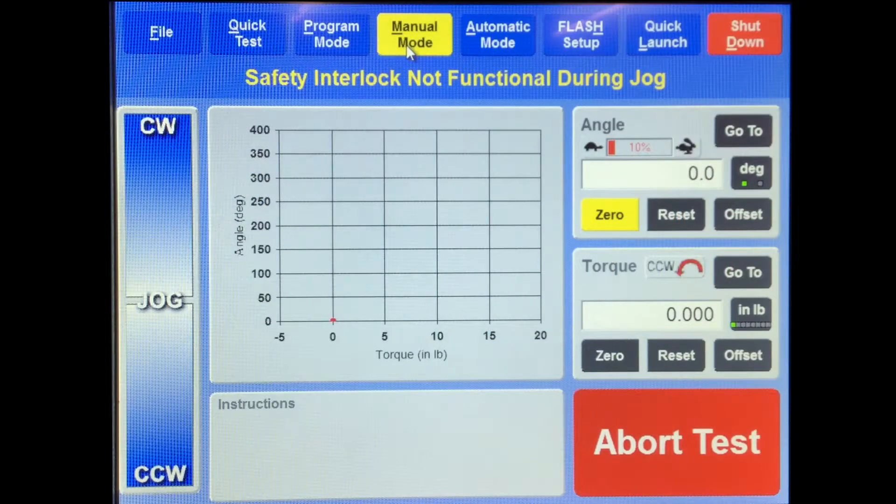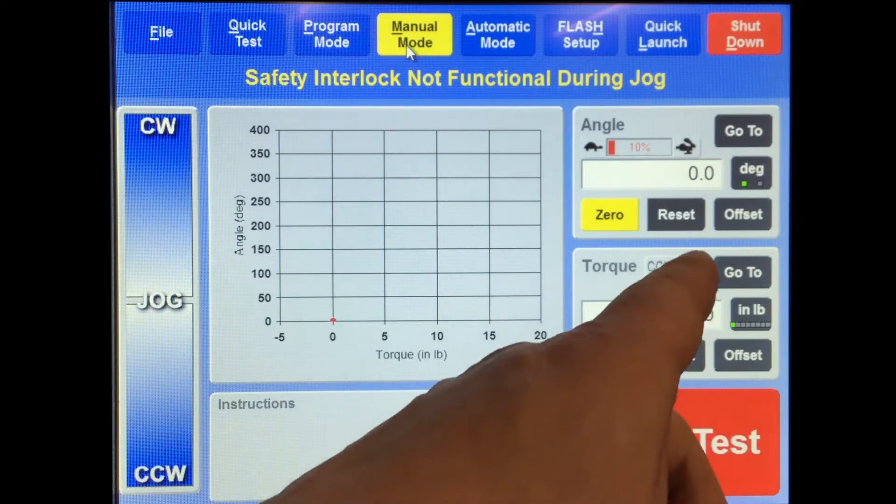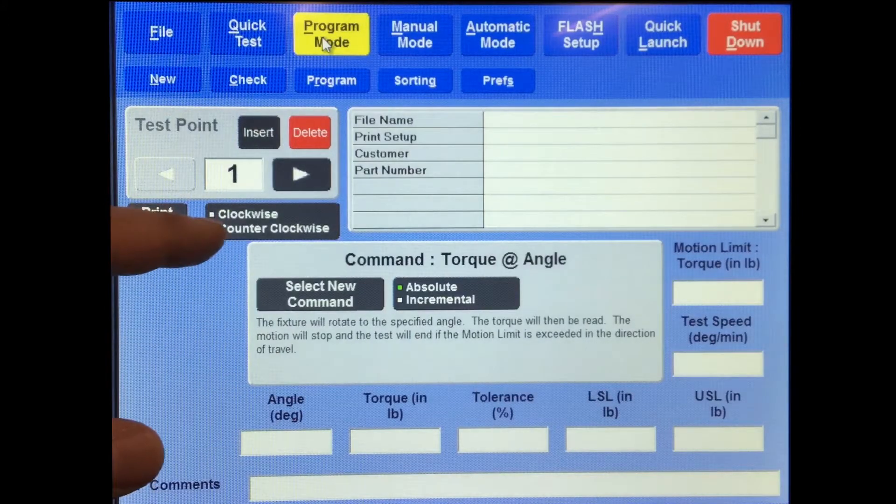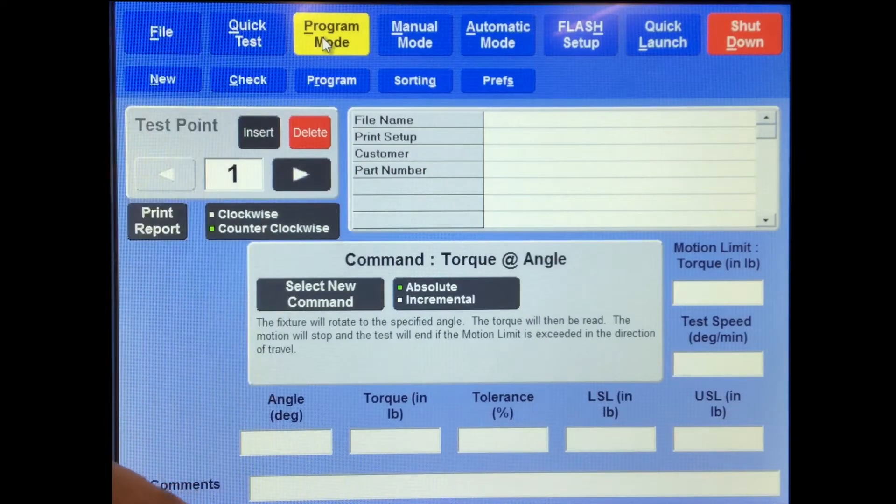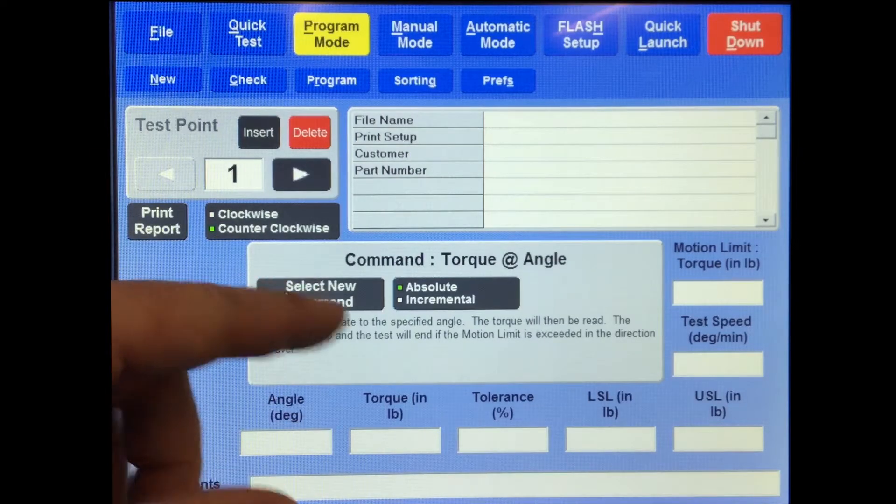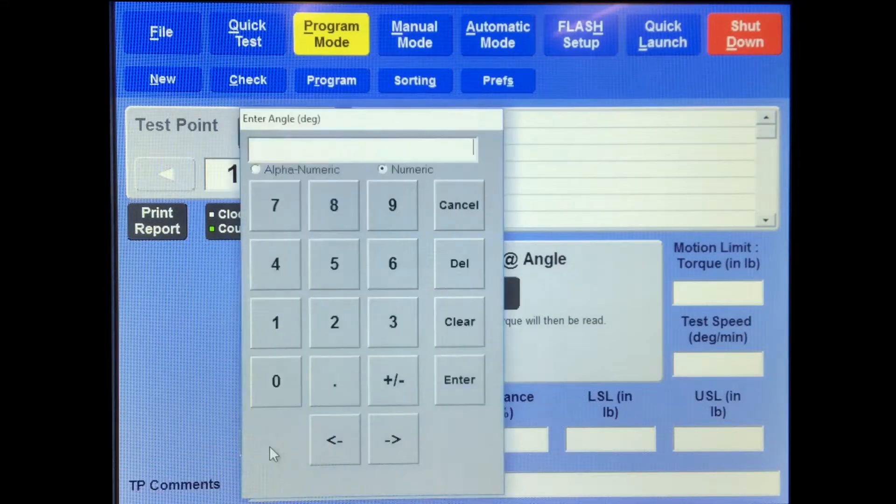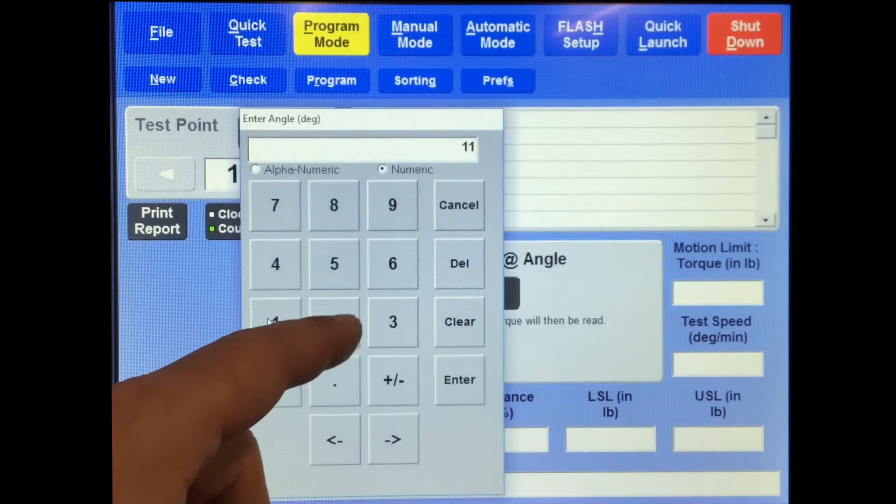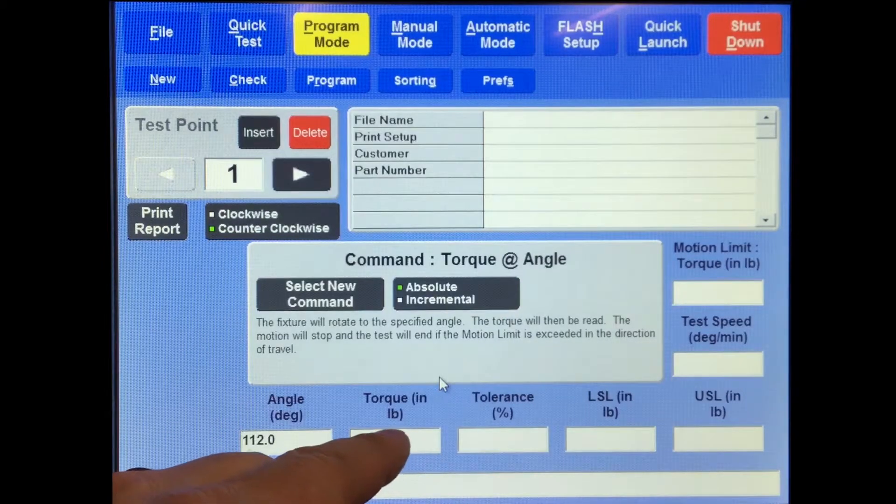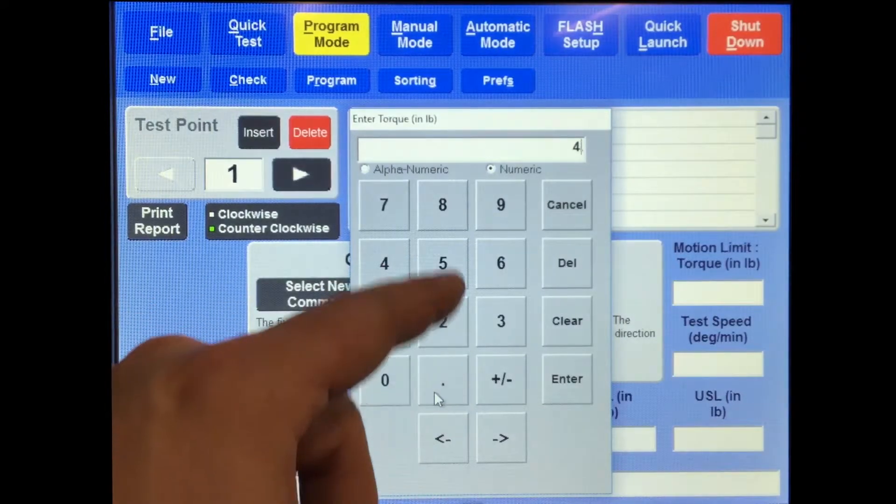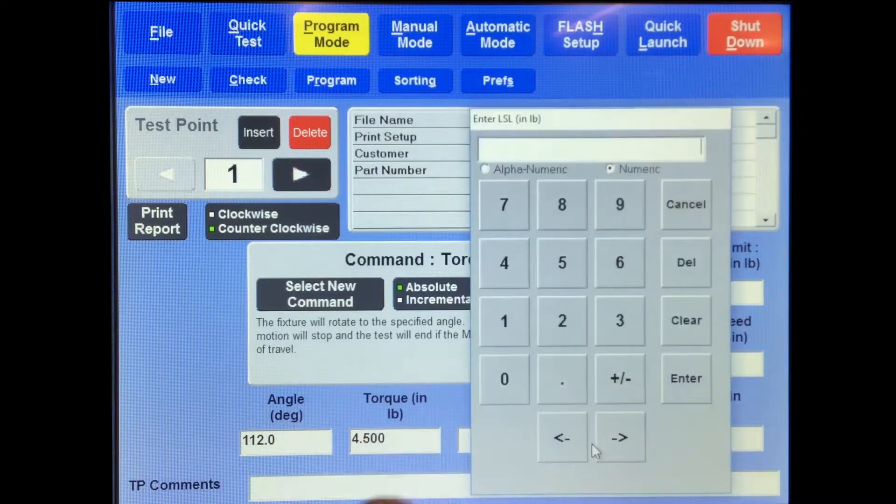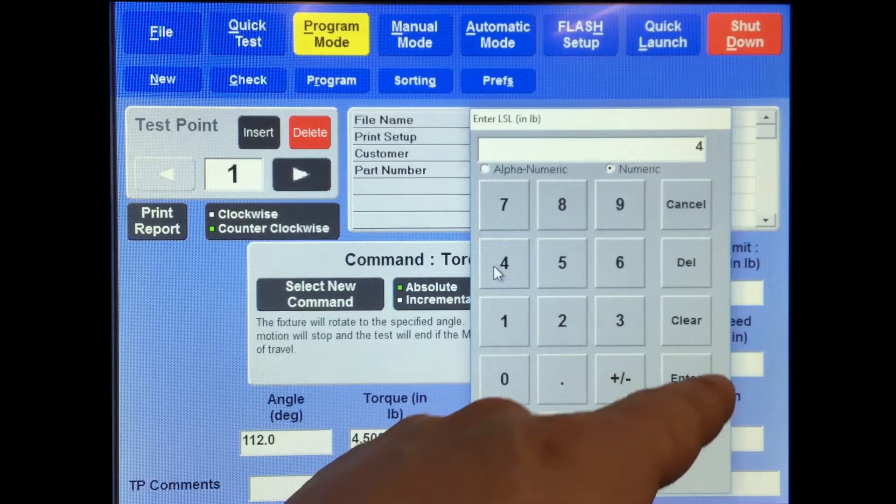So I'm going to set up a program. It's going to be done in counterclockwise, and I've already got that established, and I've got a zero angle which I like. Put a program mode, make sure that this is in counterclockwise or clockwise depending on your test. Select a new command and do torque at angle. For this particular test, I have to go to 112 degrees. The torque should be 4.5 inch pounds.